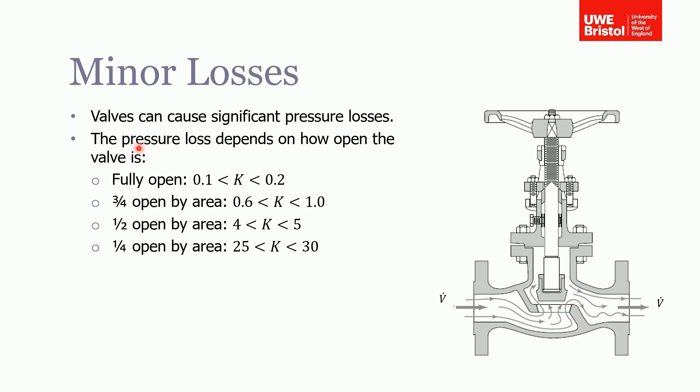That pressure drop depends on how open the valve is. If it's fully open, then it'll be much lower. Here's some typical values for a valve, and you can see as the valve is being shut down—three quarters, half, and a quarter open—the loss coefficient is increasing.